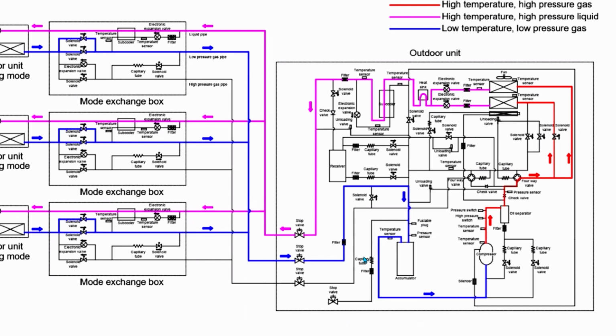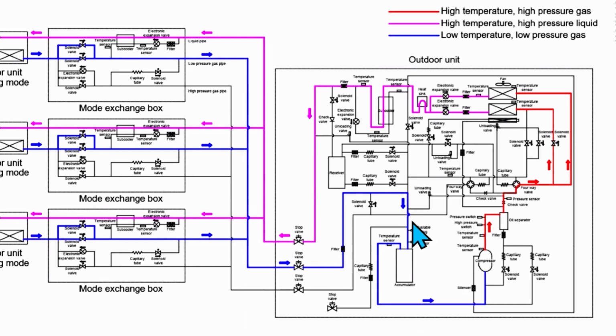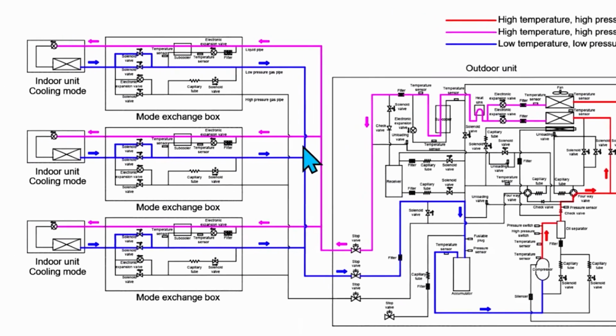That's an extra valve. If you're familiar with heat pumps at all, a lot of heat pumps have what we call a permanent suction port. That's essentially what that is. So no matter what mode you're running in, heat mode, cool mode, doesn't matter, that's always going to be suction gas. And then your liquid will always be liquid, your low pressure gas will always be low side, and your high pressure gas will always be high pressure, okay? Things change when you go into doing this as a heat pump because you're not going to have 3 pipes.